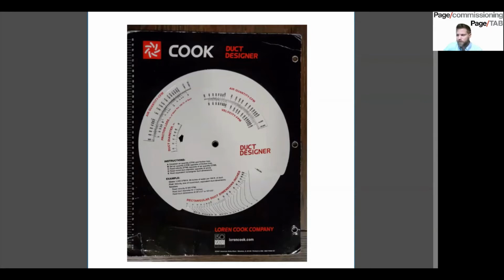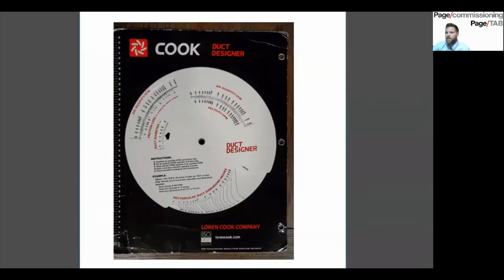Another way you can do it, if you can't find it in the specs and you don't want to call the engineer for whatever reason, you can start looking at a few of the main runs of the duct and just see what kind of friction loss they're going for on a few of the ducts. And if they're very consistent, then you can determine it based on that. But ideally, if it's not specified anywhere, just put in a call to the engineer and ask them what they're sizing their ductwork for. Is it going to be low pressure, medium pressure, or high pressure?